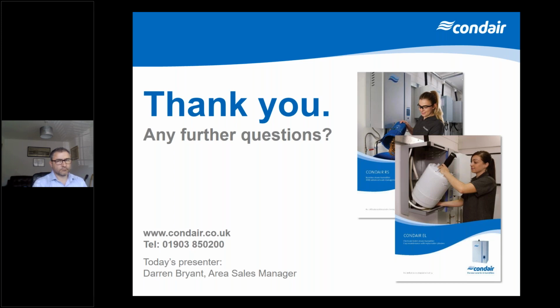So we can give you guidance, obviously, on how many times a year you would clean the unit. Now, if it's 500 microsiemens, I would be looking at maybe 3 to 4 maintenances a year to keep that system working correctly, as in a planned preventative maintenance. If you leave it less than that, you're going to be opening yourself up for maybe a cylinder replacement in between those services, and you'll have an inconsistent operation of the system.